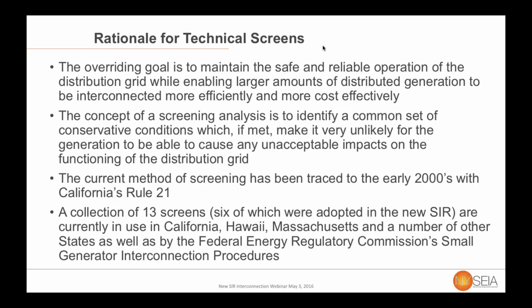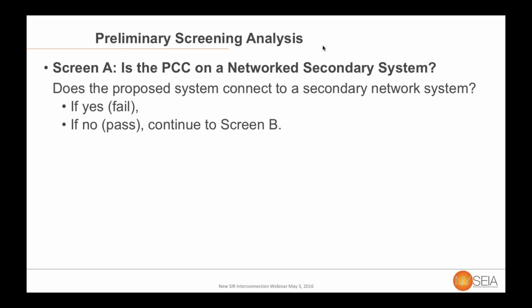to the distribution system. The current screening methodologies that are similar to what New York has just adopted trace their origins back to the late 90s, early 2000s, with California's Rule 21. These types of screens have been adopted broadly. There are a standard collection of 13 screens that, with some small modifications, have been adopted in a variety of jurisdictions, including California, Massachusetts, Hawaii, and in 2013 by the Federal Energy Regulatory Commission. Of these 13 screens, 6 that are very similar to that collection are what was adopted as the preliminary review here in New York. So what we're going to do is look at each of those 6 preliminary screens in order, talk briefly about what their rationale is, and note a couple of questions and places where we're continuing to work on this.